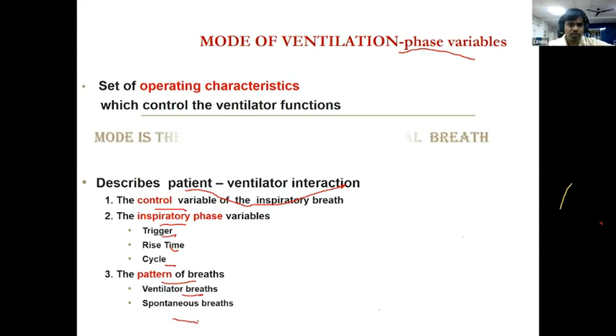So what is a variable? You see, the variable is trigger. I told you trigger. What is trigger? Trigger can be controlled breath or assisted breath. Nowadays we are always doing assisted control breath, because in previous decades they were using ventilators which continuously produce ventilation, and they won't assess the patient's effort. They will continuously produce. Nowadays everything comes under assisted control, whether it is volume control assisted or pressure control assisted.